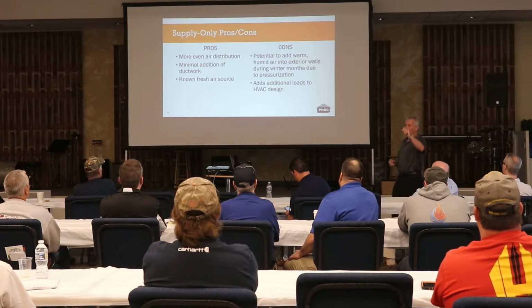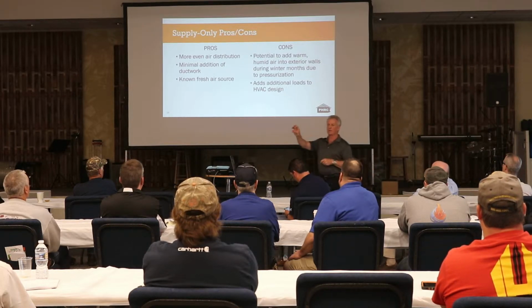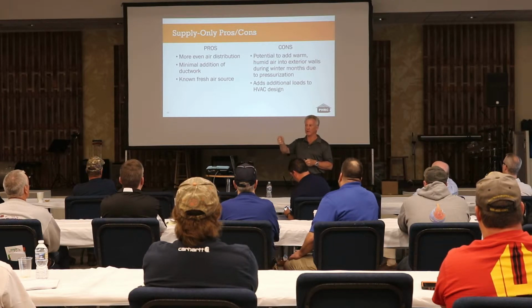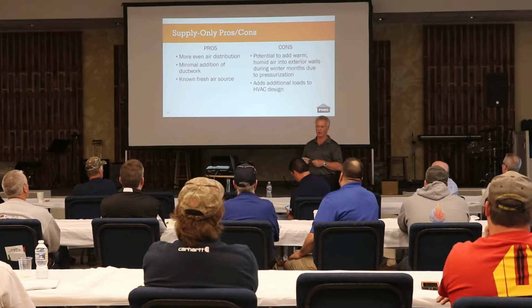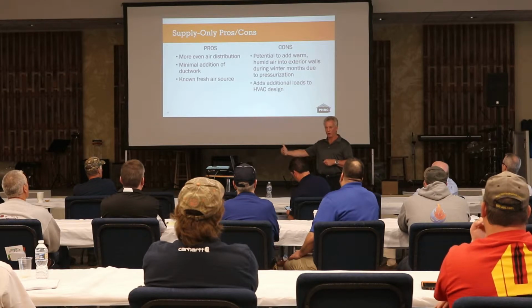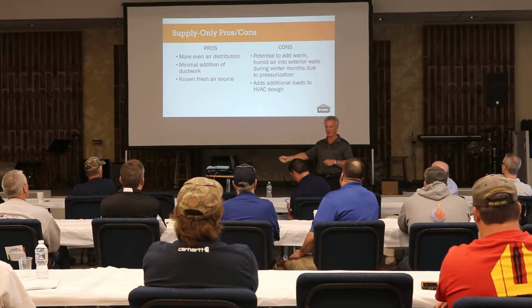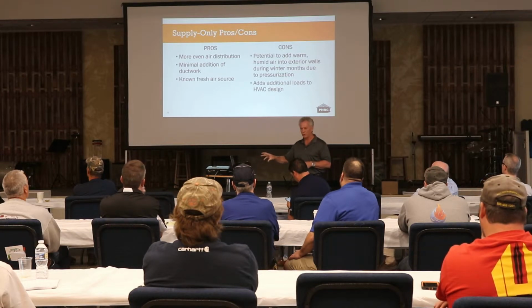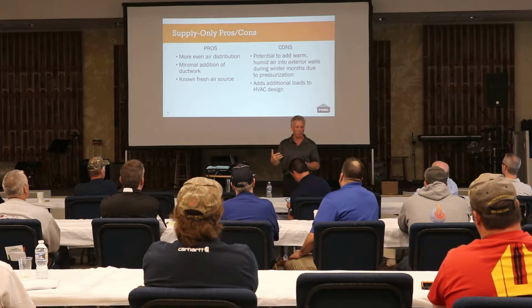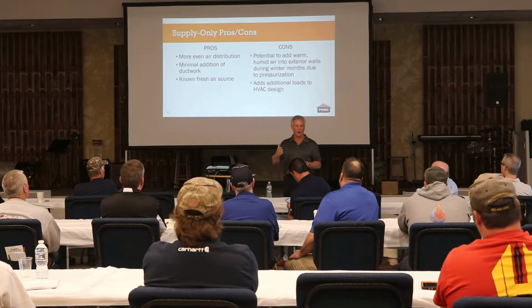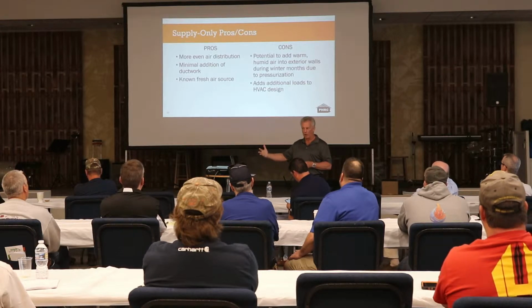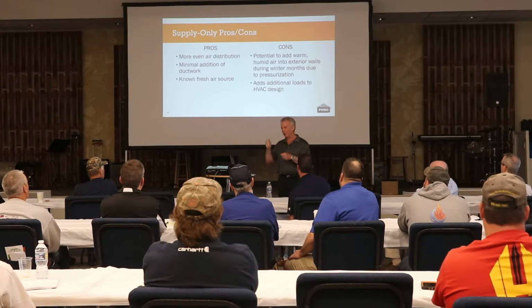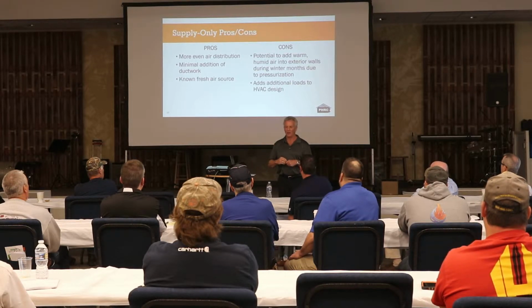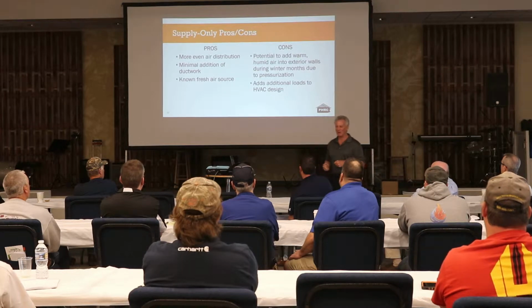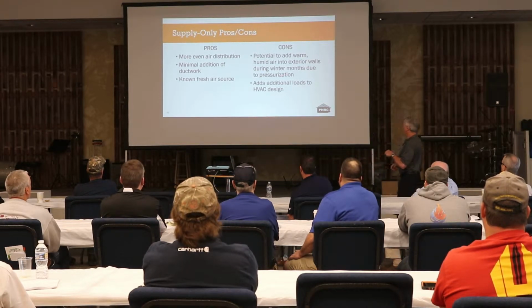And the cons we've kind of already discussed, except for this: we're adding air into the exterior walls. But the other thing is, look at the idea of a 45 CFM requirement, and now we're bringing in 100% outside, 180 CFM of untreated outside air, and we're dumping it into a return. That puts a load on the mechanical HVAC system. One of the things I hope we'll get to is a quick calc program that will show you the impact of the outside air on an existing HVAC system. I put together a quick sample of that. Ironically, the value there is 180 CFM, so we'll be able to see exactly what it adds to the loads.